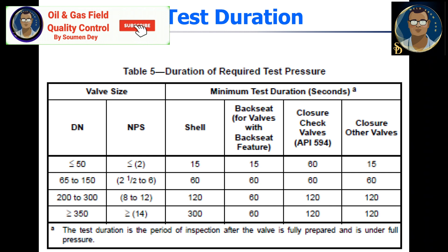Table 5 of API 598 depicts the duration of test pressure. For example, for valves less than 2 inch diameter, the shell test duration is 15 seconds, and for valves with a back seat feature it is also 15 seconds. For closure of check valves per API 594 it is 60 seconds, and for closure of other valves it is 15 seconds.